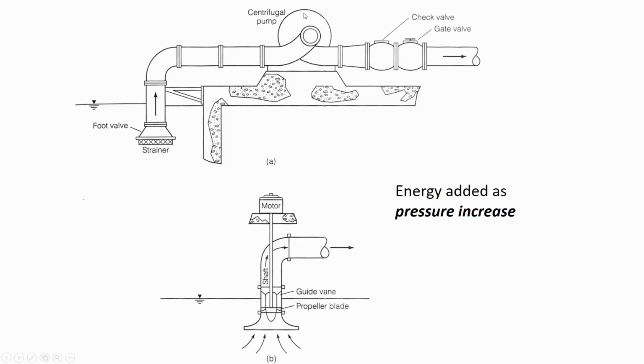I want you to remember this diagram, and remember that in the picture, the pump was pretty close to the water. We don't have any dimensions, but it's pretty close. One of the reasons it's nice to have these axial flow pumps is that sometimes the water table is really far underground, and this allows us to separate the motor from the impeller. We can have the motor at the surface where it's dry and where there's air to cool down the motor and where it's easy to access the motor for repairs. For a lot of reasons, it's easier to have the motor at the surface.